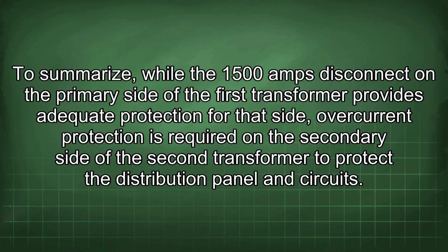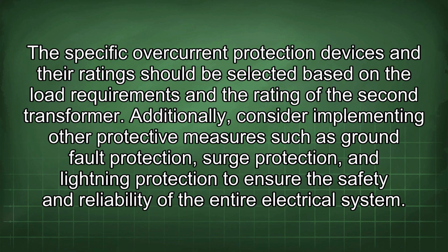activity. To summarize, while the 1500 amps disconnect on the primary side of the first transformer provides adequate protection for the primary side, overcurrent protection is required on the secondary side of the second transformer to protect the distribution panel and circuits. The specific overcurrent protection devices and their ratings should be selected based on the load requirements and the rating of the second transformer. Additionally, consider implementing other protective measures such as ground fault protection, surge protection, and lightning protection to ensure the safety and reliability of the entire electrical system.